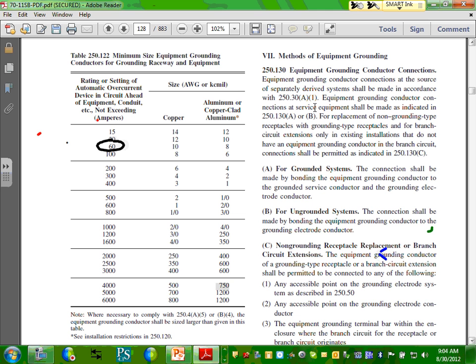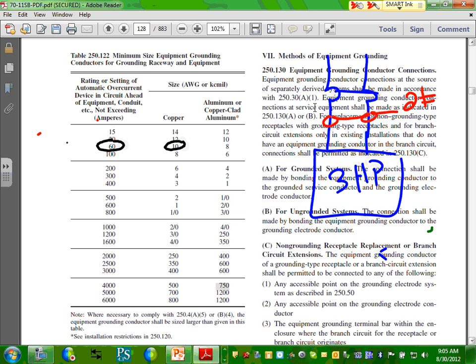To 60. And what's the conductor size? Number 10. Now, before you write number 10, what was the phase conductors? So I have here a conductor. I'm going to write the circuit here. And here's my machine, my motor, my 3 horsepower pump, okay? These 2 conductors, guys, were what? 2 conductors number 12 AWG THHW. Cool. And I need to pull an equipment grounding conductor here. Here's my ground from the panel, and I will pull an equipment grounding conductor.